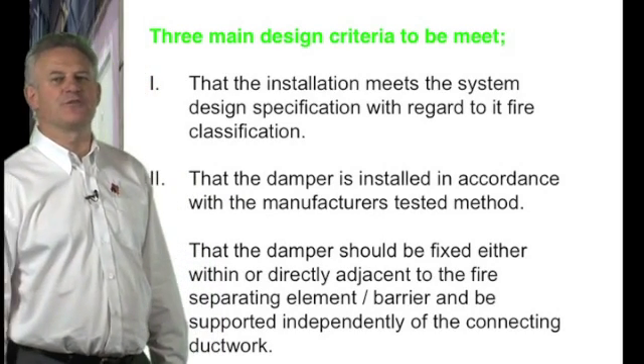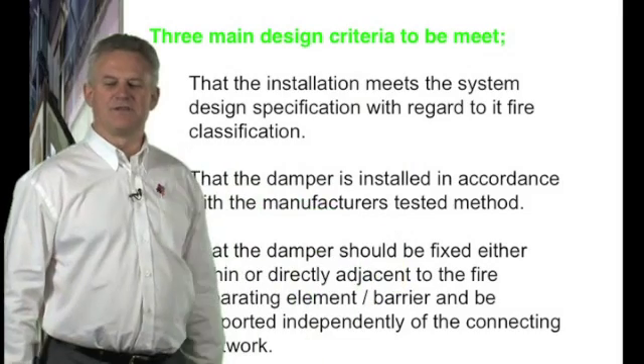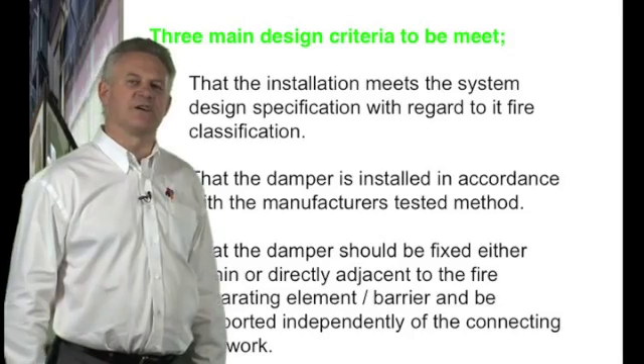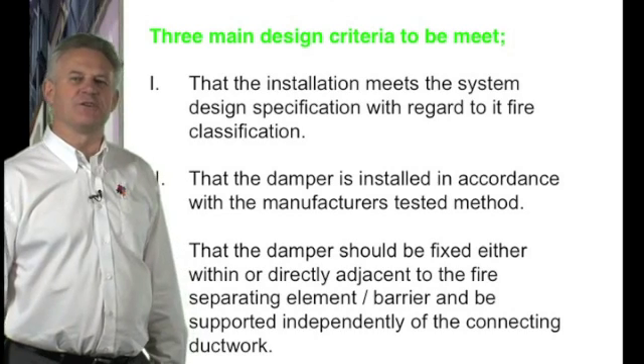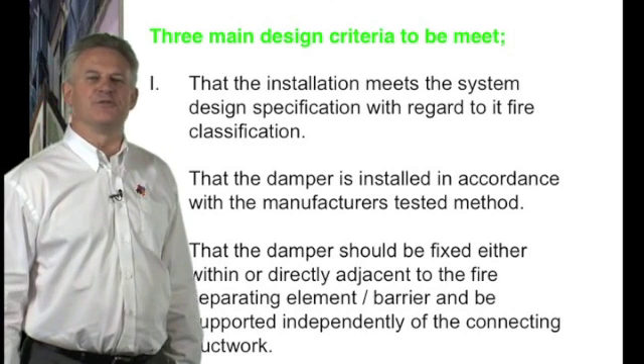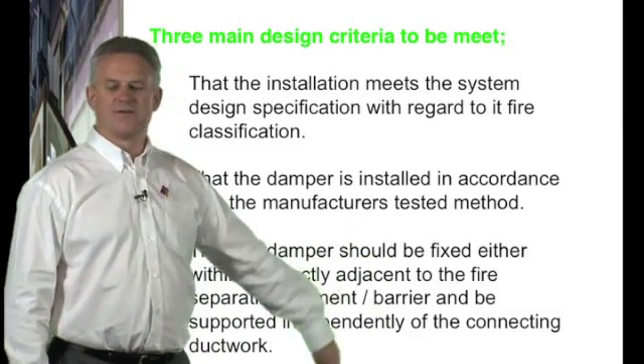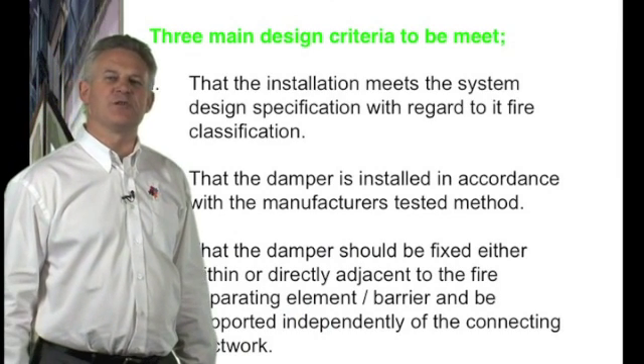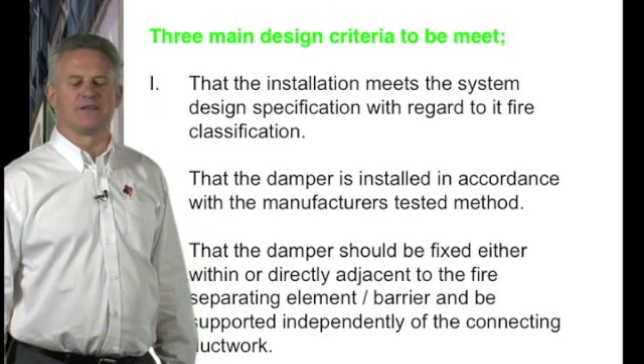The installation methods must meet the system design specification with regard to fire classification. The damper and installation must be in accordance with the manufacturer's tested methods, with the damper fixed either within or directly adjacent to the barrier and independently supported from the connecting ductwork.